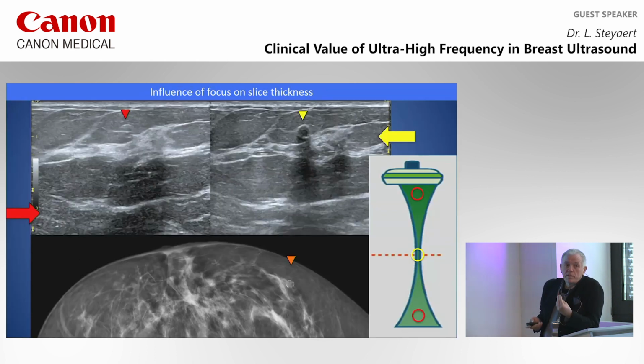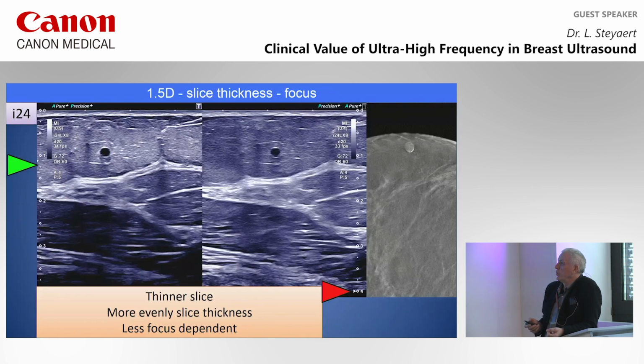The influence of the focus is very important on a standard probe because of the different shape of the slice thickness. Here is an example of a small calcified oil cyst. If the focus is okay, then we see it very well. If the focus is much lower, then you don't see it anymore because of the thickness of the slice, the partial volume effect. So quality is not only linked to the frequency alone, it is also linked to the probe technology.